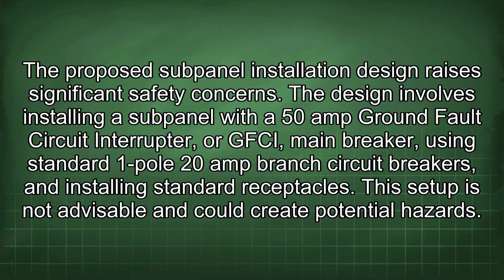The proposed subpanel installation design raises significant safety concerns. The design involves installing a subpanel with a 50-amp ground fault circuit interrupter, or GFCI, main breaker, using standard 1-pole 20-amp branch circuit breakers and installing standard receptacles. This setup is not advisable and could create potential hazards.